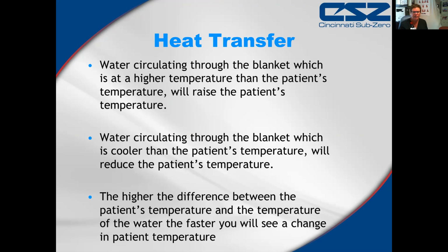So water circulating through the blanket, when the temperature of the water is cooler than the patient, will obviously cool the patient. The opposite is true when the water is warmer than the patient. It will warm the patient. So the greater the difference between the patient's temperature and the temperature of the machine, the quicker it will cool or warm the patient. So the bigger difference is the fastest means of cooling or warming.